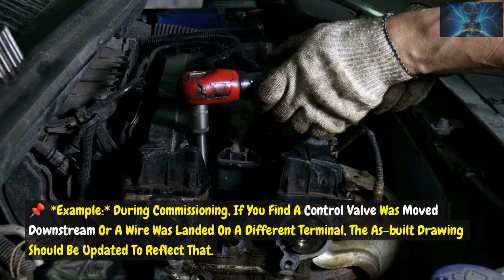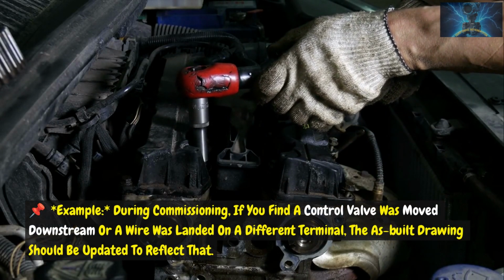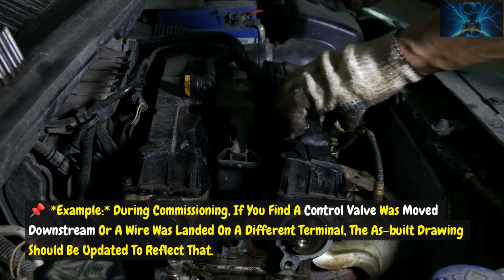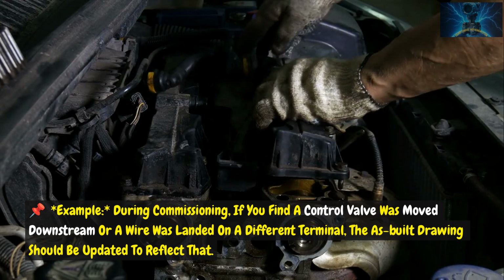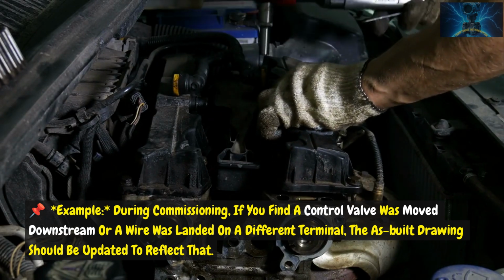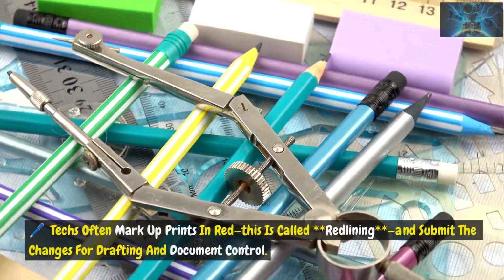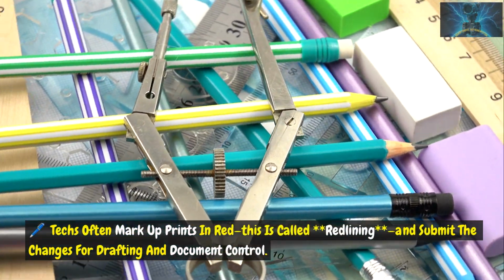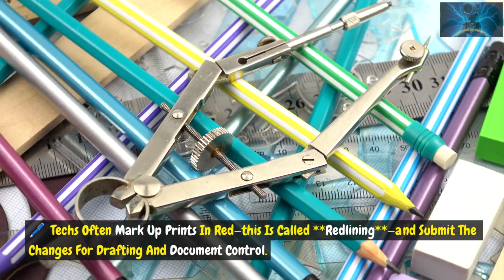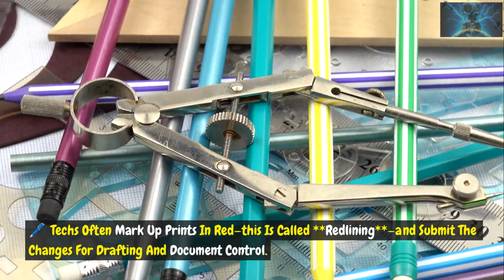Example: during commissioning, if you find a control valve was moved downstream or a wire was landed on a different terminal, the as-built drawing should be updated to reflect that. Techs often mark up prints in red, this is called redlining, and submit the changes for drafting and document control.